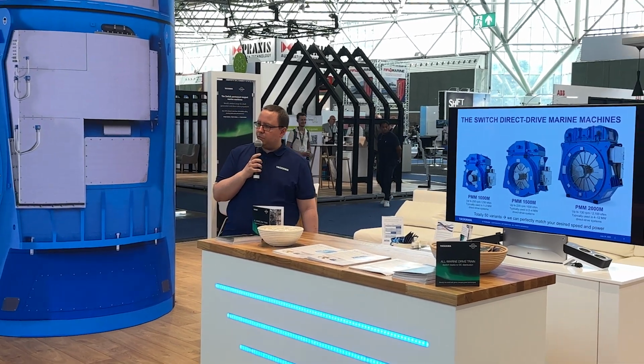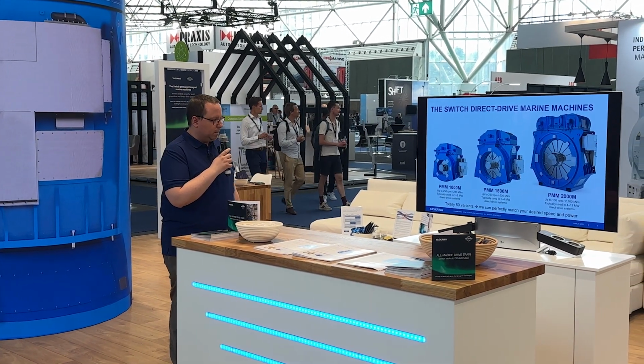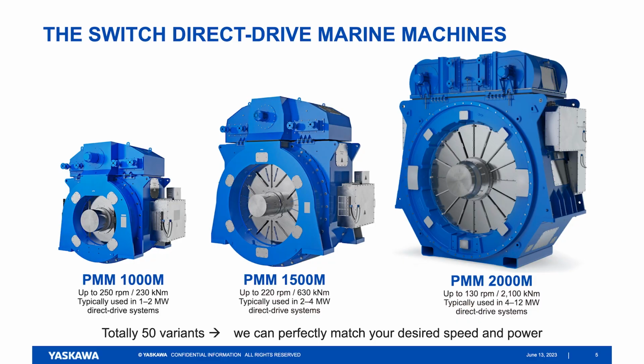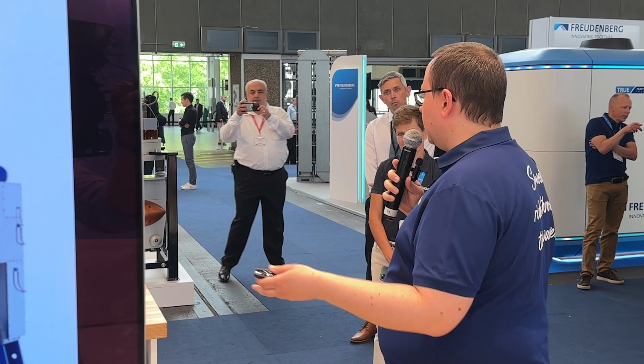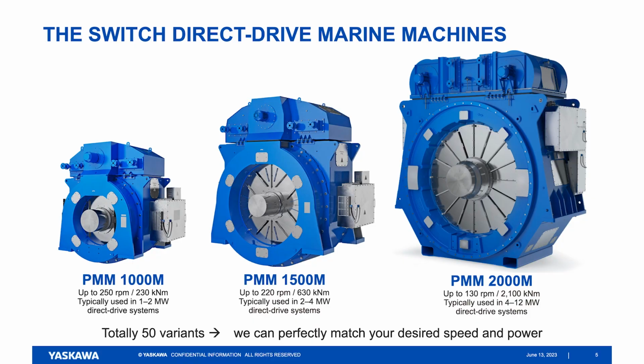So this is what we have to offer for you. We have at the moment 3 different sizes: PMM 1000, 1500 and 2000. PMM stands for permanent magnet machine, 1000 is the shaft height in millimeters, and M stands for marine. We provide these machines over different speed ranges, depending on your power and torque applications. These are the 3 options we can choose from, and then we can play a little with the stack lengths of the machines to get the required power for your application. The big one, for example, goes up to 12 megawatts at the moment. So these are quite powerful machines.